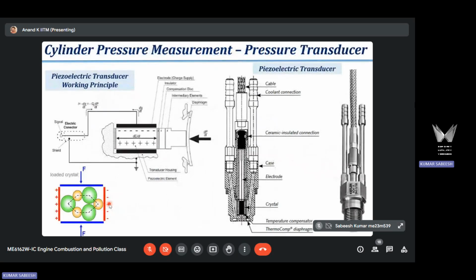So now let us look at the pressure measurement. What is the principle followed, and how do we get the pressure signal by using this sensor? The sensor that we use is called a pressure transducer. This is also called a pressure pickup or a pressure sensor. These are different names for the same instrument. So this is a photographic view, and this is a sectional view of the pressure transducer. And this line diagram provides the operating principle of this sensor. This line sketch indicates the operating principle of this pressure transducer.